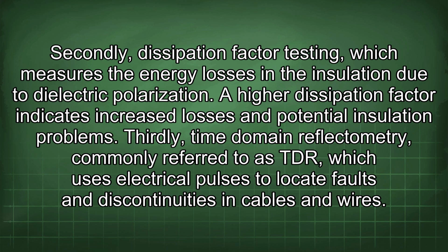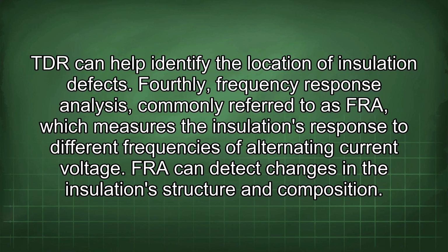Secondly, dissipation factor testing, which measures the energy losses in the insulation due to dielectric polarization. A higher dissipation factor indicates increased losses and potential insulation problems. Thirdly, time domain reflectometry, commonly referred to as TDR, which uses electrical pulses to locate faults and discontinuities in cables and wires. TDR can help identify the location of insulation defects.